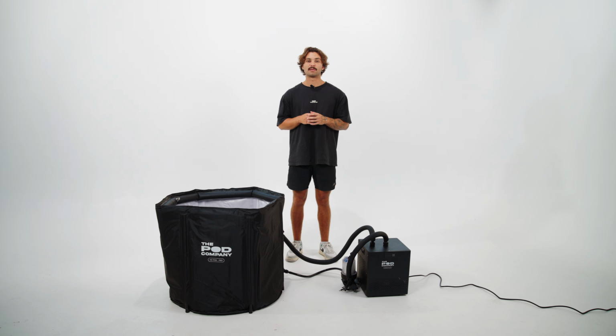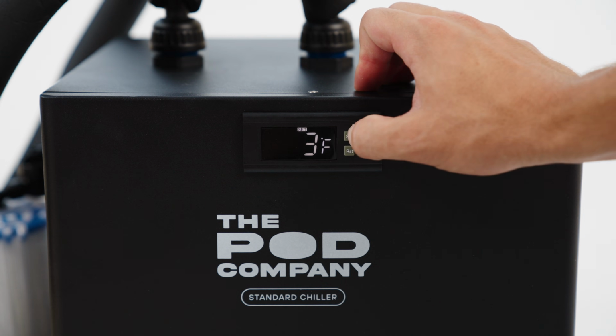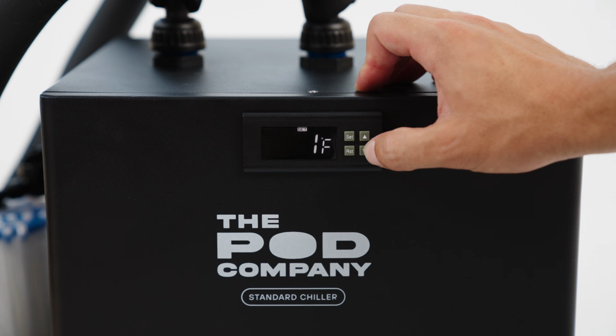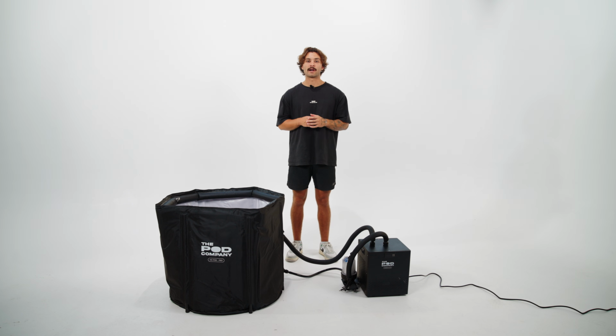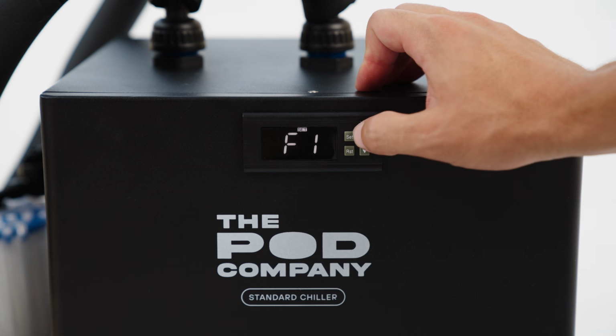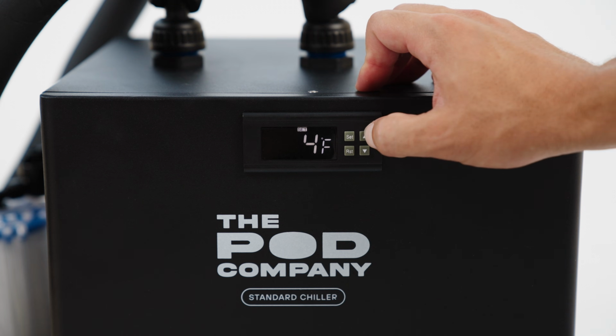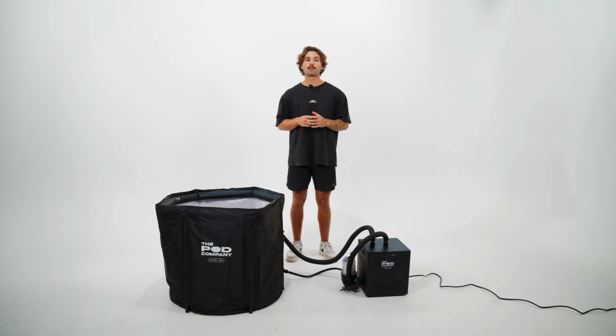While this setting can be adjusted, finding the right balance is key. Setting F1 too low will cause the compressor to run non-stop, which can lead to unnecessary wear and tear. Setting F1 too high may delay the compressor from activating, leaving your water warmer than desired. For efficient cooling and to maintain the correct temperature, we recommend keeping F1 at the default setting unless you have a specific reason to modify it.